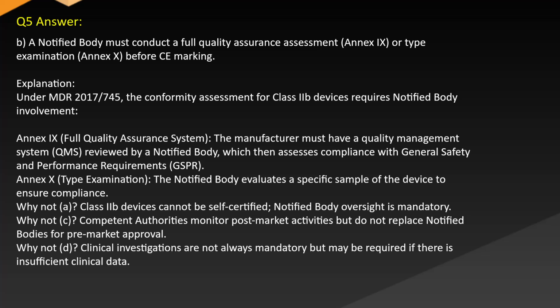Why not A? Class IIb devices cannot be self-certified. Notified body oversight is mandatory. Why not C? Competent authorities monitor post-market activities, but do not replace notified bodies for pre-market approval. Why not D? Clinical investigations are not always mandatory, but may be required if there is insufficient clinical data.